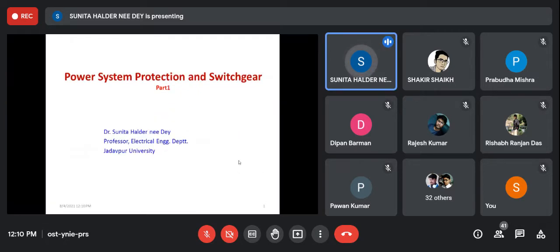Here we shall start from switch gear protection. Why is it named switch gear and protection? Actually, there is one part which will disconnect the heavy power system. You know, power system is a heavy power device. In normal operating condition, power may be transferred from 0 to 500 megawatt or more than that, and voltage level may be up to 750 kV. So you have to disconnect a particular part of that system when any unhealthy situation arises.